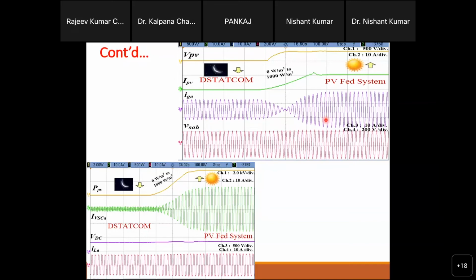And here we have the nonlinear loads. That's why we are going for the DStatCom. But if you are operating with a PV park and you don't have any local loads, at that time you can operate as a StatCom also. Then you will see this will generate only the reactive currents, meaning your converter and capacitor will take power from the grid and convert it into reactive power.